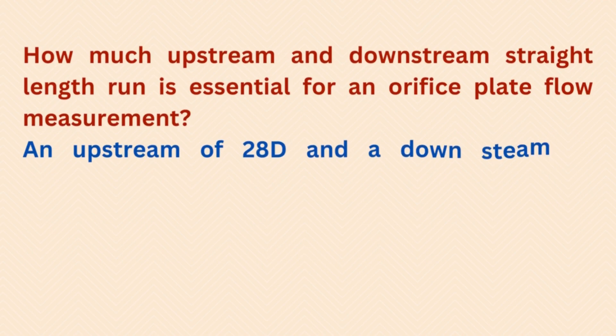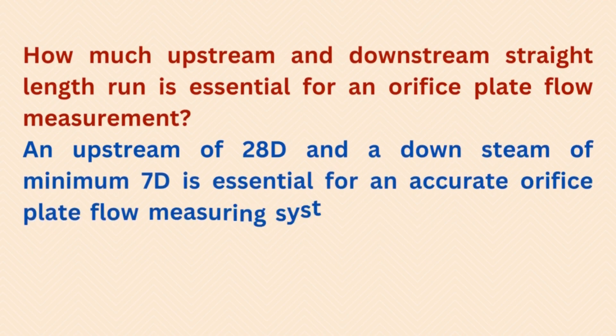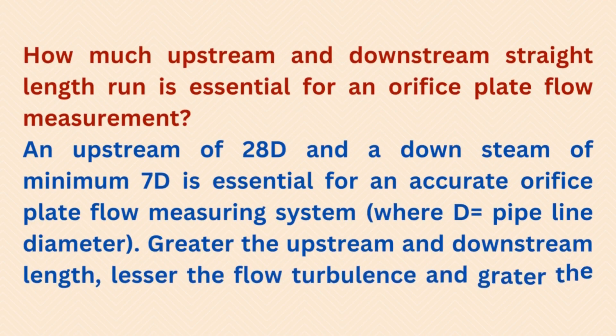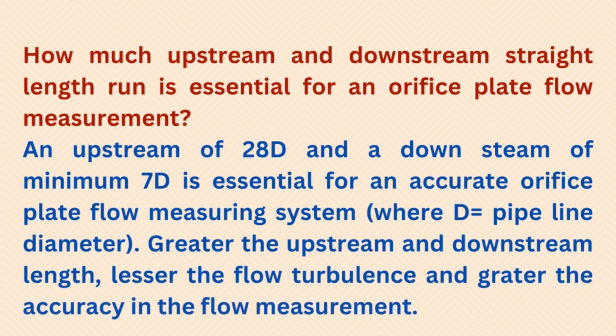How much upstream and downstream straight length run is essential for an orifice plate flow measurement? An upstream of 28D and a downstream of minimum 7D is essential for an accurate orifice plate flow measuring system, where D is equal to the pipeline diameter. Greater the upstream and downstream length, lesser the flow turbulence and greater the accuracy in flow measurement.